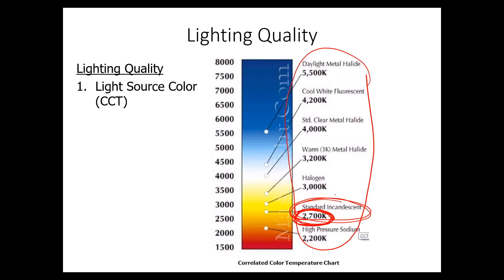What's counterintuitive about this is the higher you go in temperature, the more blue the light appears. We often call that cool white — around 4100 Kelvin — although technically it's actually a warmer temperature than standard incandescent lamp color. This is important because it establishes the ambiance of an environment.